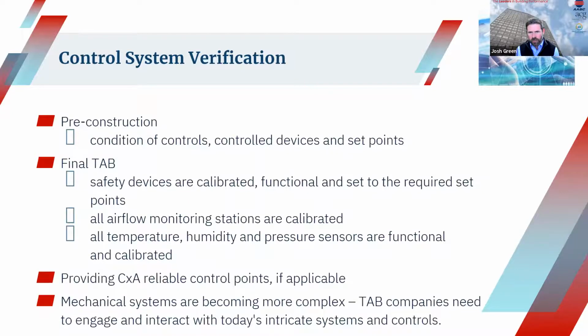Also, during final TAB, we verify that all the safety devices, airflow measuring stations, and control sensors are installed, operational, and reading correctly. With as much time as our technicians spend in front of the equipment, who better to do this than the TAB industry? If the CxA is involved, if there's commissioning on the project, the TAB process will provide those reliable control points for the system commissioning. If there's no commissioning involved in the project, the TAB firm, I believe, should at least be verifying that the sequences are meeting the design intent.